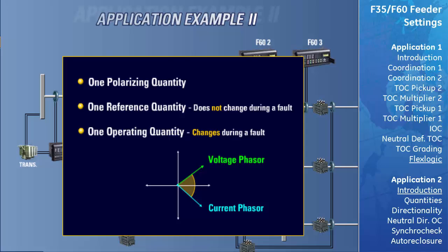We will only examine how the phase directional overcurrent detection method is applied to phase A. The same methodology is used on phases B and C at the same time.